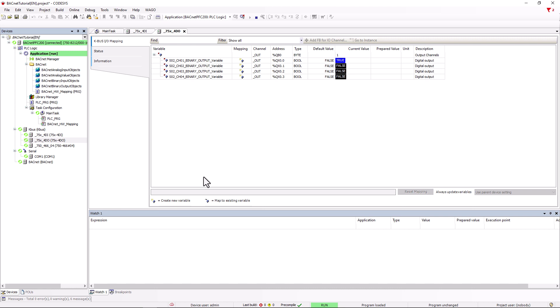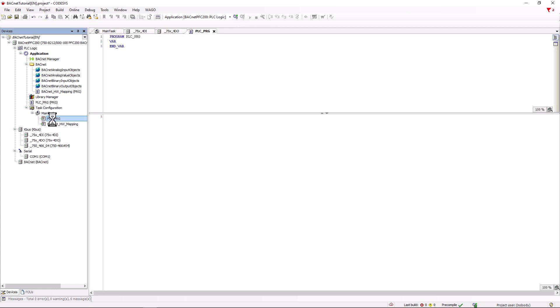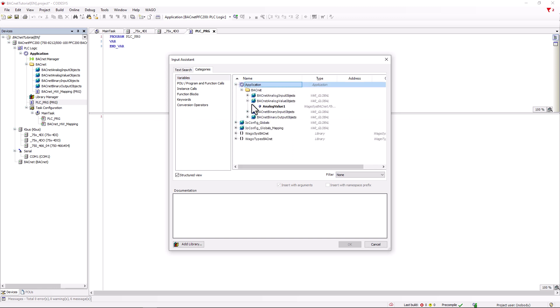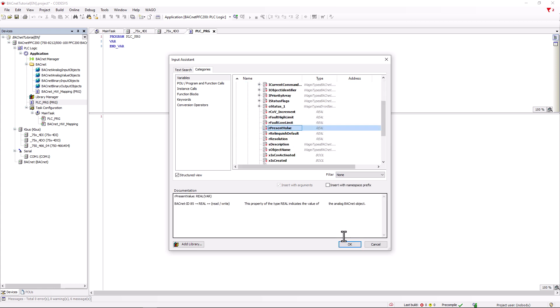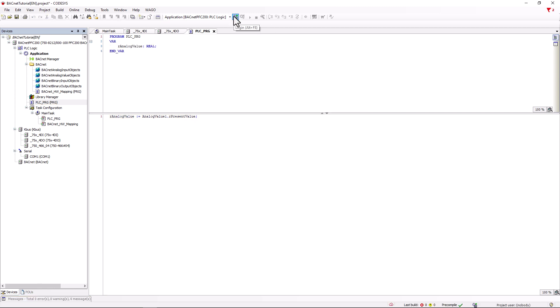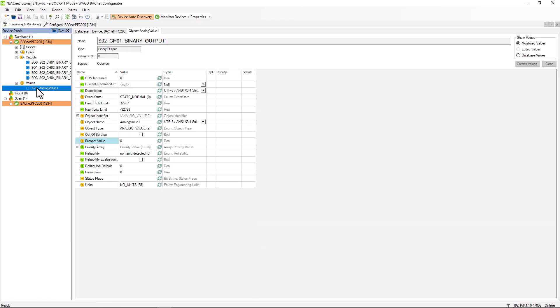The non-native additionally created analog value can also be found in the BACnet objects folder in the GVL BACnet analog value objects. We can use this in the PLCPRG by assigning and declaring a variable to it. We insert the analog value with F2 from the path: Application folder > BACnet > GVL BACnet analog value objects, for example with the property rPresentValue. We assign this value to a variable and declare it. Via this variable rAnalogValue, the property presentValue of the BACnet object is now read cyclically.